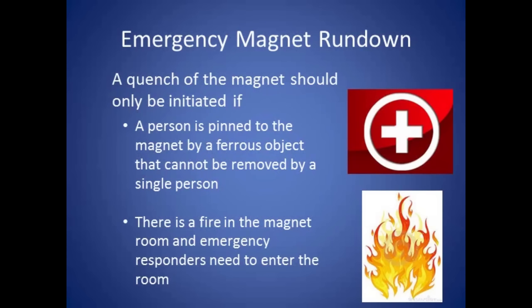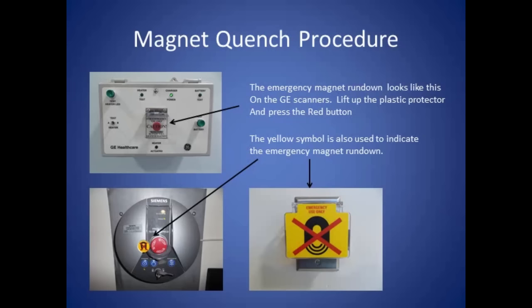The emergency quench procedure is done by pressing the emergency rundown button. On GE scanners, simply lift the plastic cover and press the red button. On other systems, such as Philips and Siemens, the yellow symbol is also used to indicate the emergency magnet rundown.